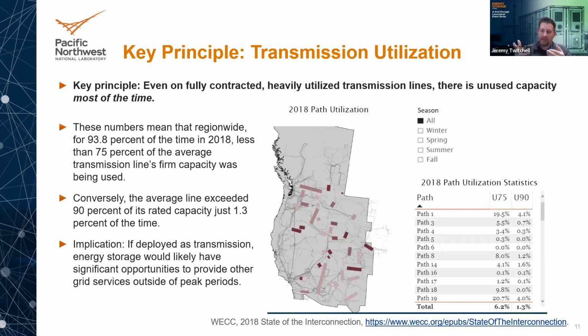So the implication here is that if we deploy energy storage as a transmission asset, there's going to be a lot of time where it's not needed to provide that transmission service, and it could be doing other things. If you think about it, this makes sense, right? We build the grid based on peak needs plus reserve margins, but we're only at that peak a few hours a year. So the rest of the time we have excess capacity, excess transmission, and if it's just a transmission line, it's being used or it's not. But if it's storage, when it's not being used as transmission, it can go do other things.